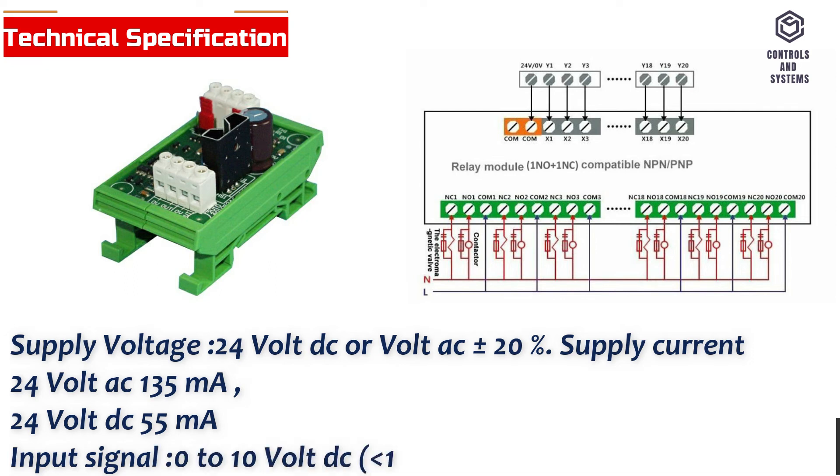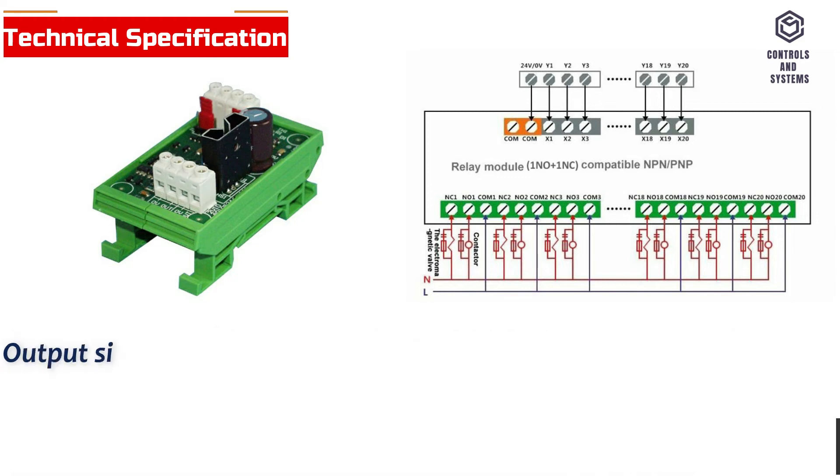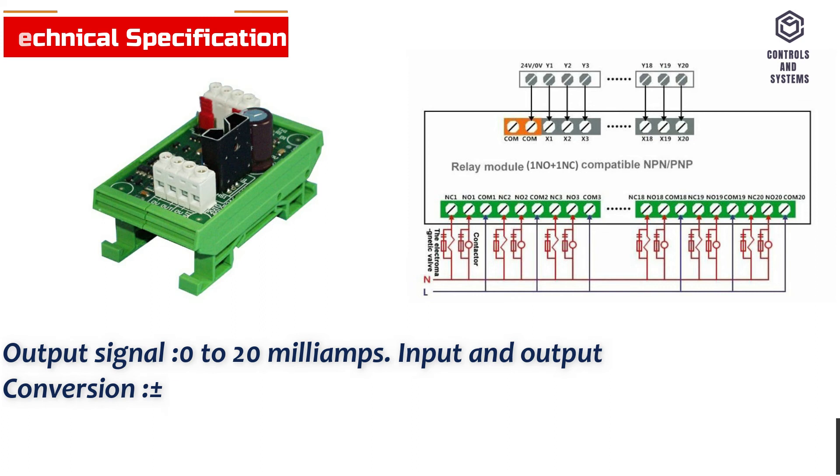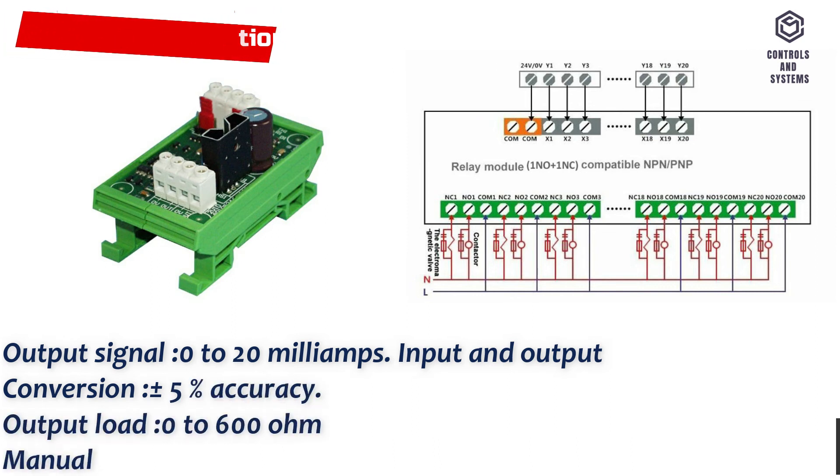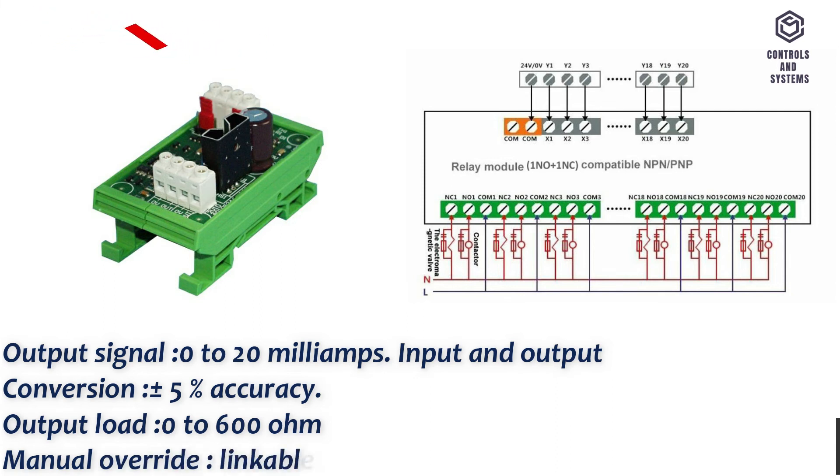Input signal 0 to 10 volt DC, less than 1 milliamp per channel. Output signal 0 to 20 milliamps. Input and output conversion plus minus 5% accuracy. Output load 0 to 600 ohm. Manual override linkable auto on/off.